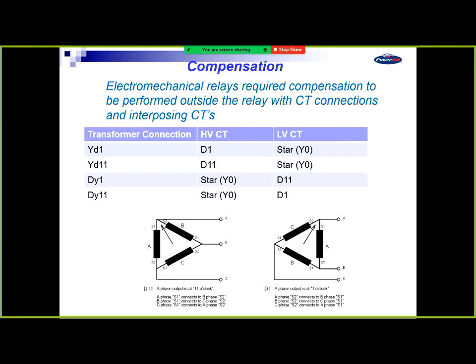So the old ways that used to be done, if you had a YD1 transformer, your HV CTs had to be connected in delta, so star delta, the YD stands for, and the LV CTs had to be in a star, and so on down through the different ones. So you had to have that consideration when connecting up your CTs, and that was always a source of human error. If they connected up wrongly, you would trip spuriously. They usually found that out when they turned the transformer back on. They get a trip. Go back, check their circuitry, got one back to front.